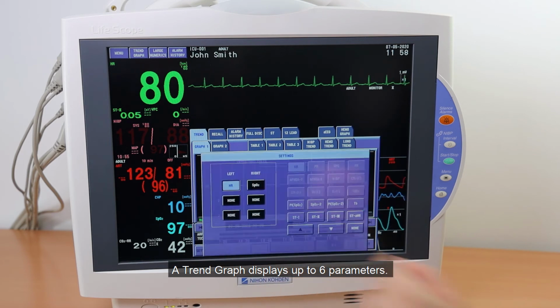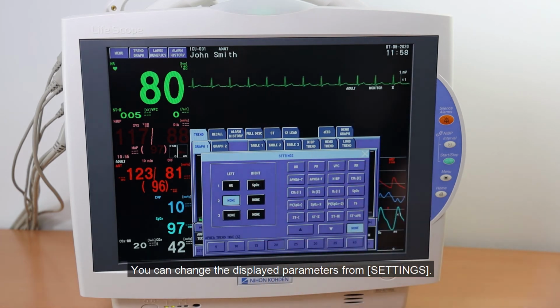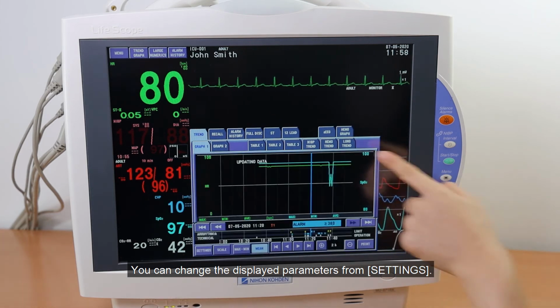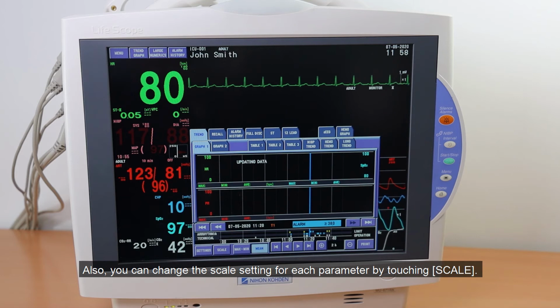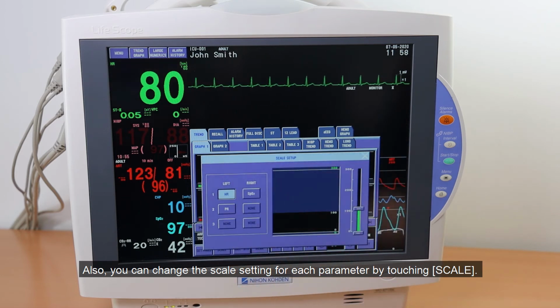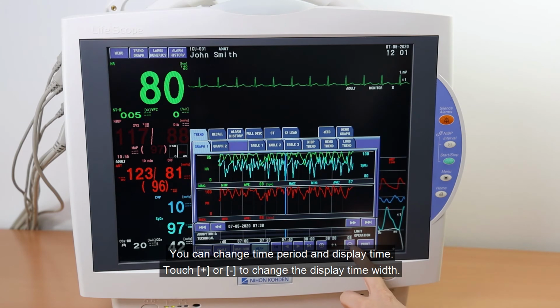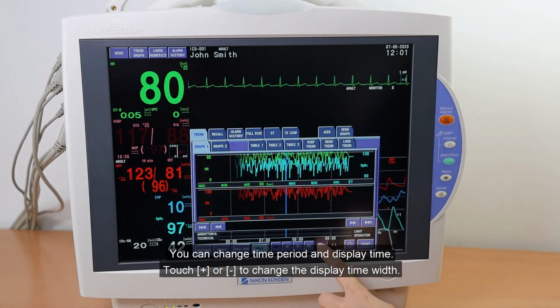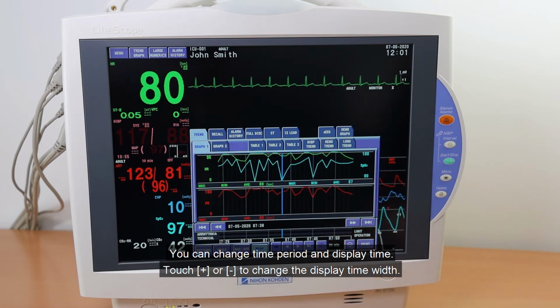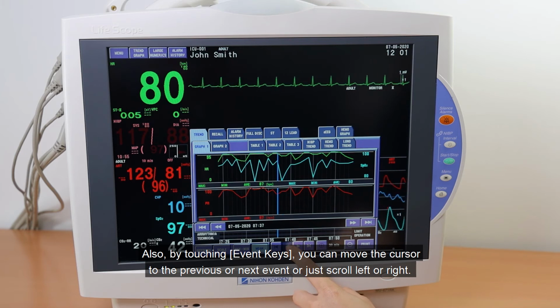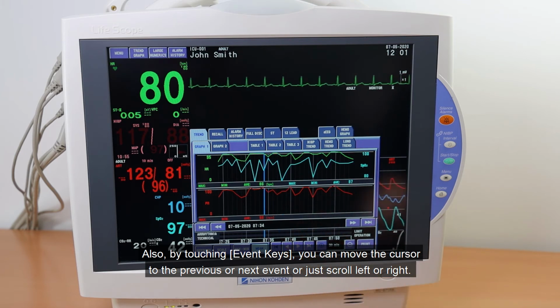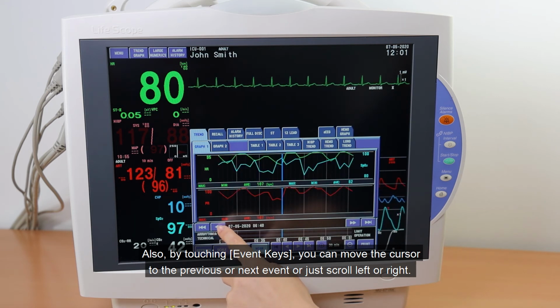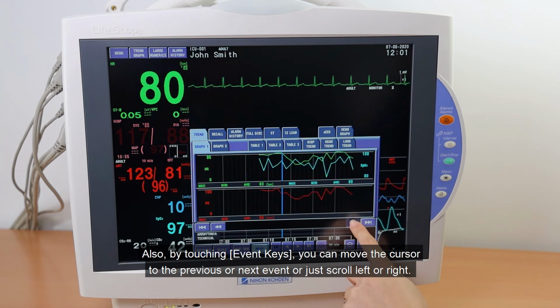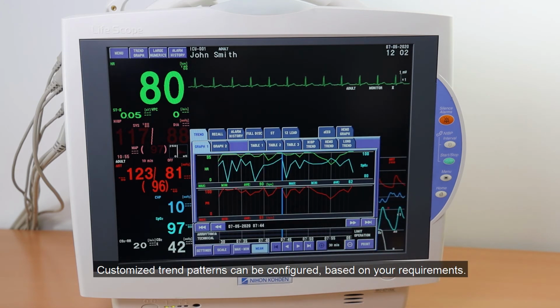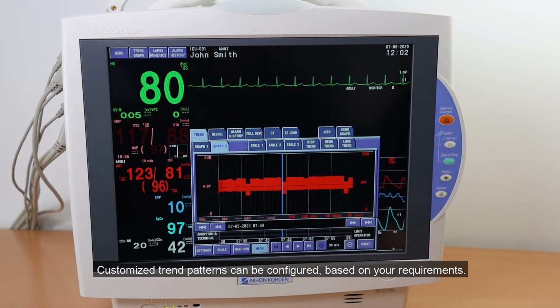A trend graph displays up to 6 parameters. You can change the displayed parameters from Settings. Also, you can change the scale setting for each parameter by touching Scale. You can change time period and display time. Touch plus or minus to change the display time width. Also, by touching Event keys, you can move the cursor to the previous or next event, or just scroll left or right. Customized trend patterns can be configured based on your requirements.